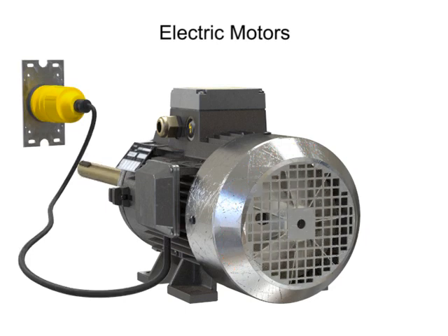Since these multi-directional motors are equally efficient in either direction, there's no standard direction of rotation. Therefore, when a three-phase motor is first connected, it may run in either direction, and technicians must be careful to install it properly.